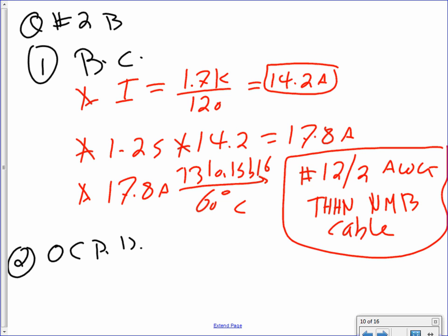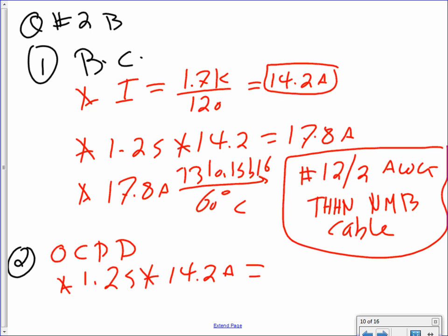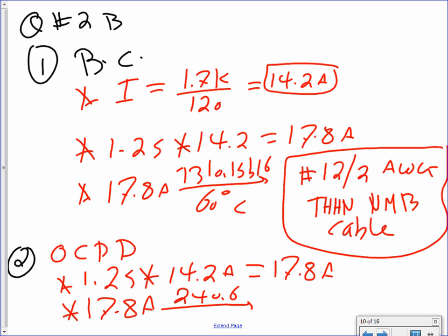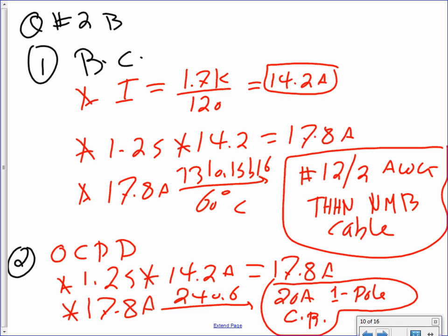Overcurrent protection device. Shall we do the overcurrent protection device? For the overcurrent protection device, guys, we'll do basically the same calculation. 1.25, multiply that by 14.2 amps, and that will get you 17.8 amps. You take the 17.8 amps to 240.6, and that will get you how many amps? 20 amps, single pole. 20 amp single pole circuit breaker, not two pole.